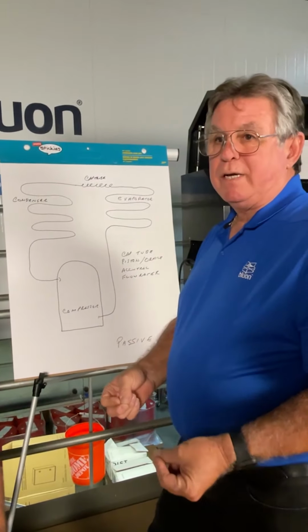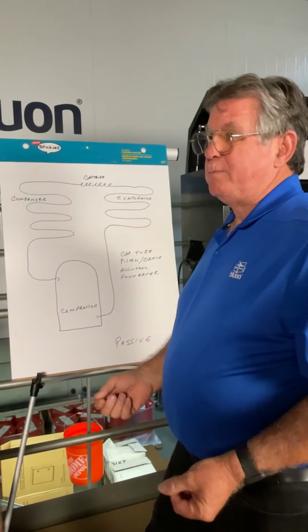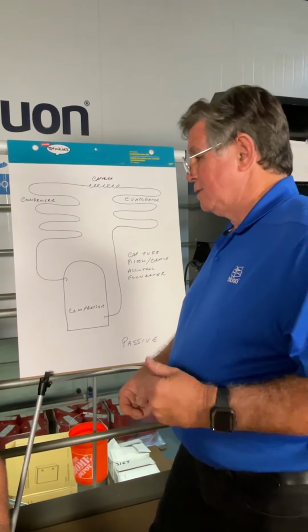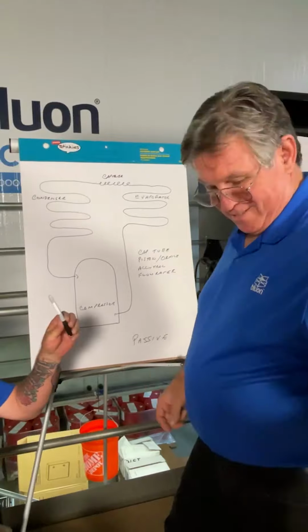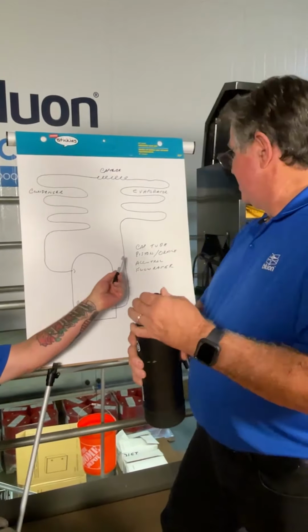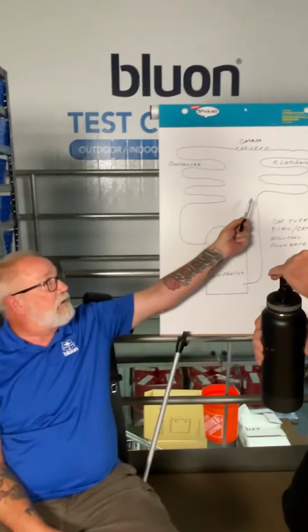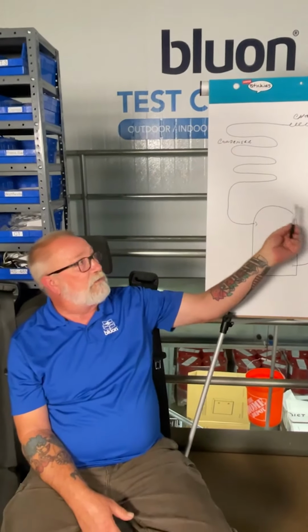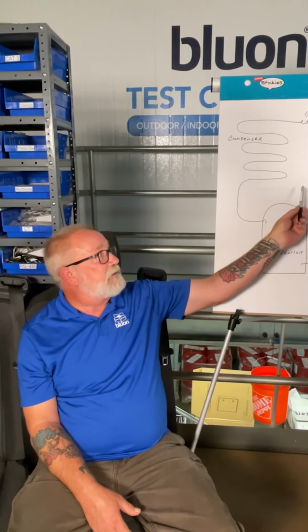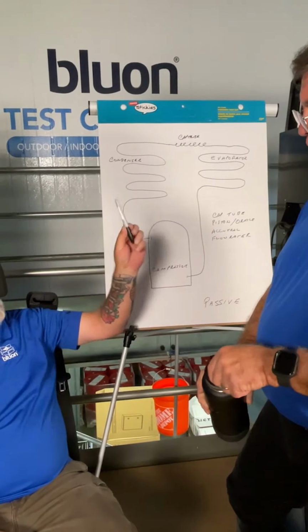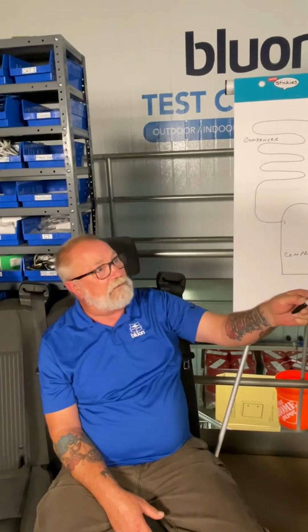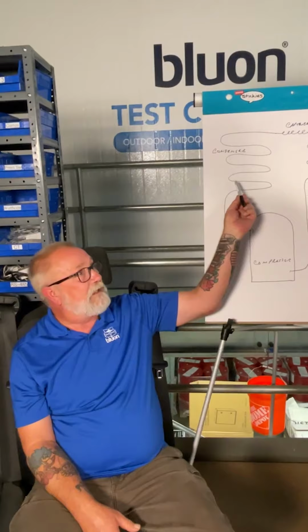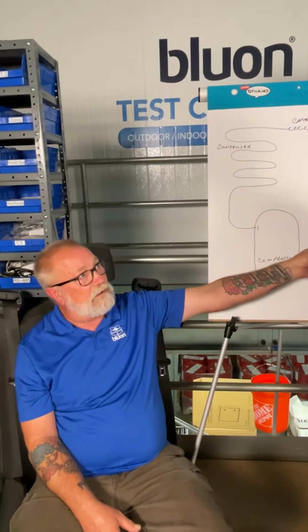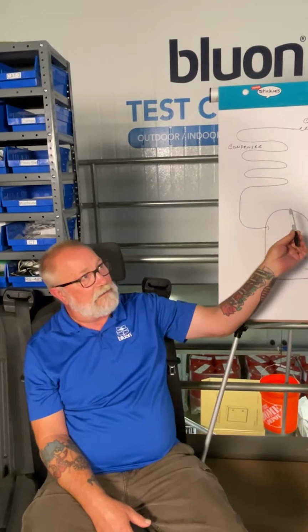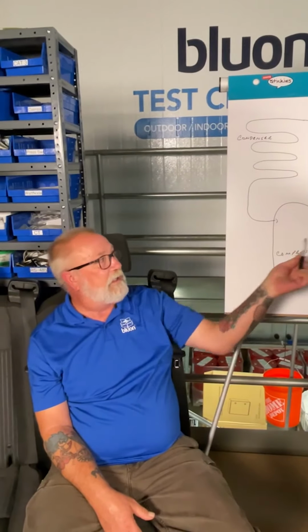So what they did is they started off with these automatic expansion valves, which were kind of a disaster. But go ahead. Before we get into that, you hit a key point. As it's going through, you really have no control over that. And so that's why we use the target superheat calculator, because it will take the outdoor conditions, the indoor conditions at that time to tell you what your superheat at the compressor should be on the suction line.